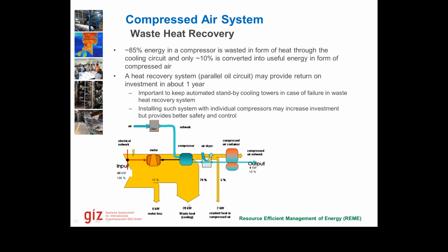If we have a boiler or an air or a thermal oil heater nearby, we could directly heat up their intake air using this air. Or if we don't have it, we could heat up water and then feed this water to a boiler or other processes. But the critical aspect would be whether we have a big system or a small system. If we have a small system, it might not give us a useful amount of energy, but if we have a multi-compressor system or large compressors like we usually have in weaving and spinning, there we can gain a lot of energy. The problem is where to use that energy.